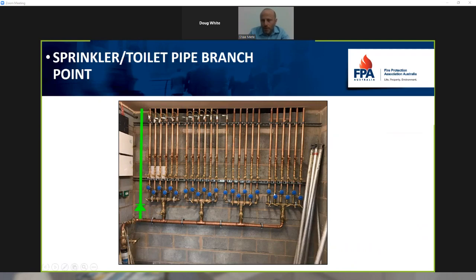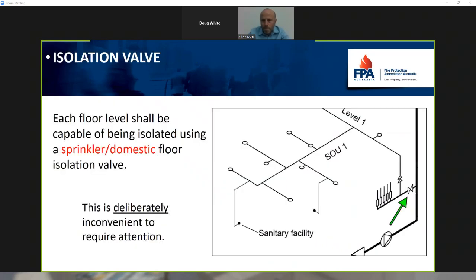So I just want to stress that point. If you have to replace the sprinkler head, you shut this valve off, which will shut off all drinking water to the floor. Now, I know that sounds like an incredible inconvenience, and it is. It's designed to be an inconvenience because it means that we have to work a little bit faster and smarter about how we're going to do these repairs and replacements, and we can't shut water supplies to residential buildings and leave them off overnight or for extended periods of time. So that's the schematic there. That's the valve that I'm talking about. You shut this valve off, all of the system goes down, including your water meters. This is deliberately inconvenient to require the attention.